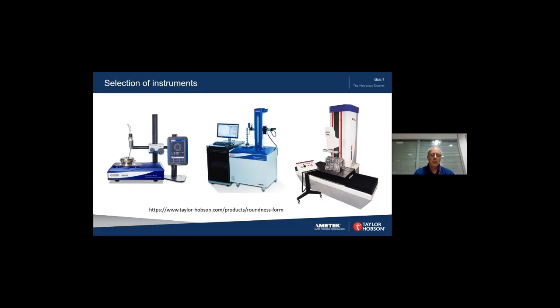In the center of this image is the Talyrond 500 series instrument, which is a floor-standing rotating workpiece instrument with a very high degree of automation. This enables the user to create measurement programs for frequent measurements. This particular instrument also includes precision axial and radial axes, allowing several additional measurements to be made other than just roundness.